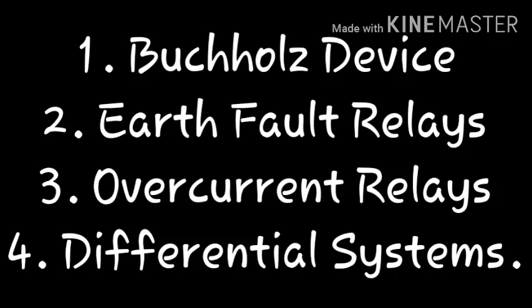The complete protection of a transformer usually requires a combination of these systems. The choice of a particular combination may depend upon several factors such as size of transformer, type of cooling, location of transformer in the network, nature of load supplied, and importance of service for which the transformer is required.